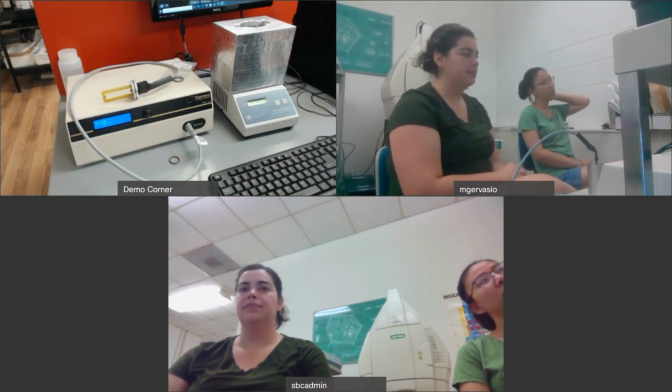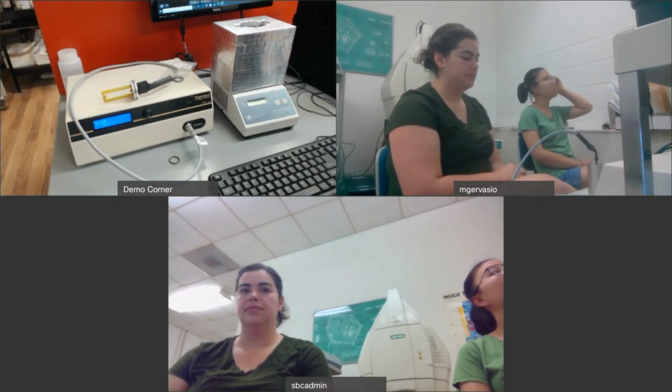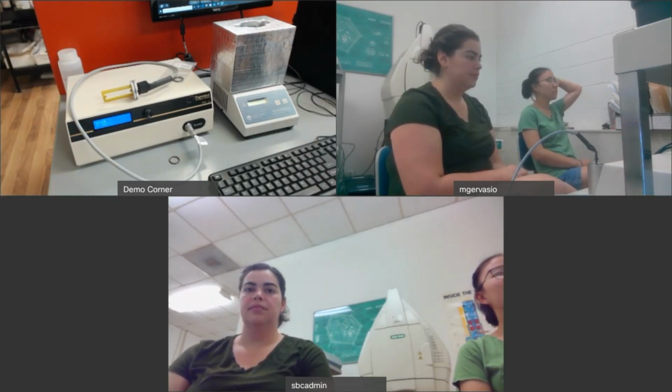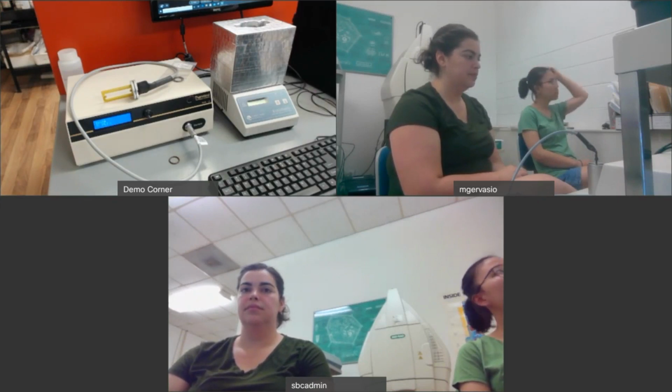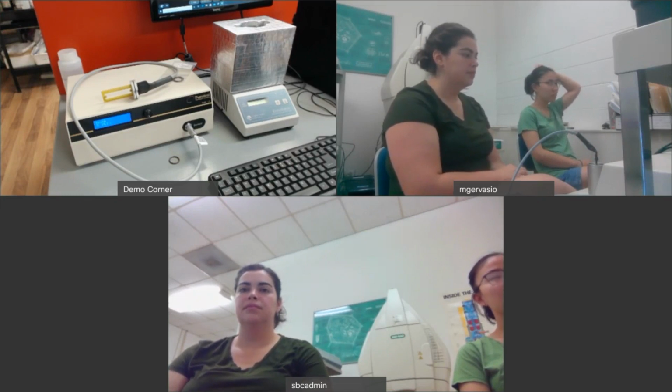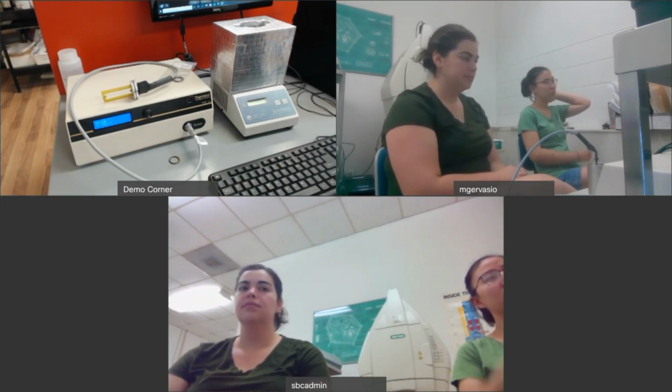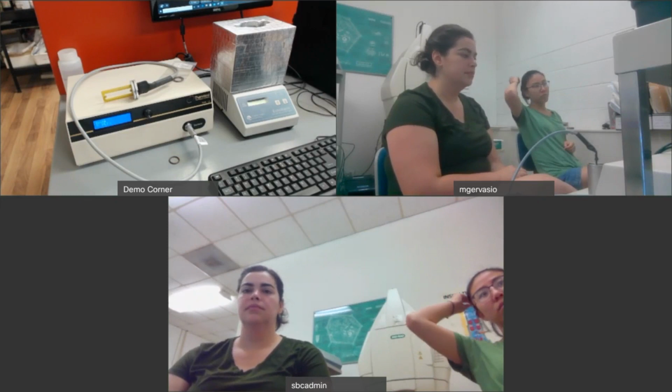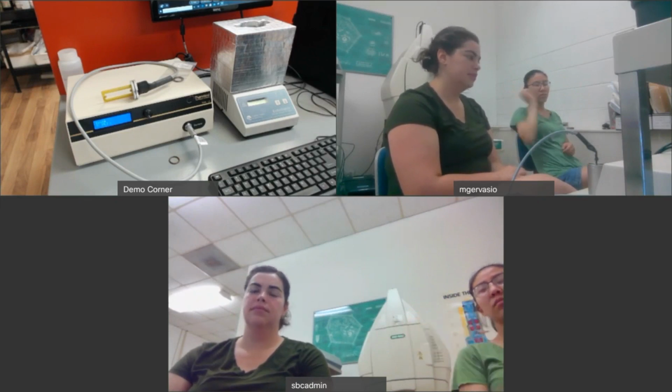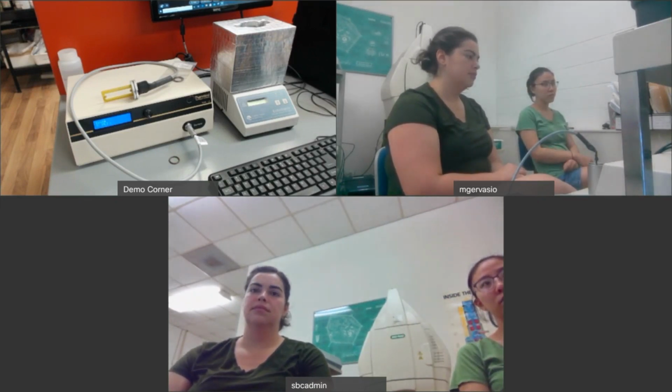Then we correct, because what it is doing is a correction for the length of the wire. Now it's trying to correct again the value and be closer, and then you calibrate it again. So that was advice for future use in case you need to replace the wire if something happens, because now the value was extremely high.